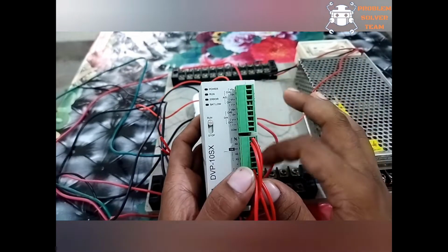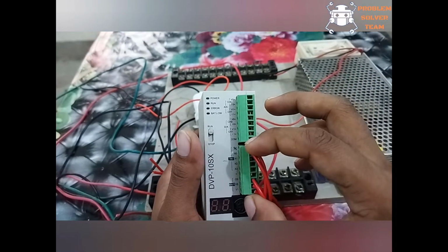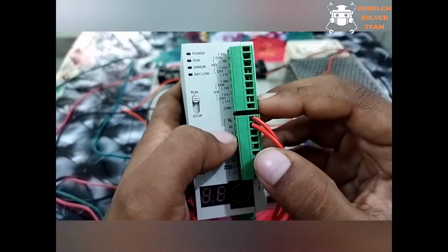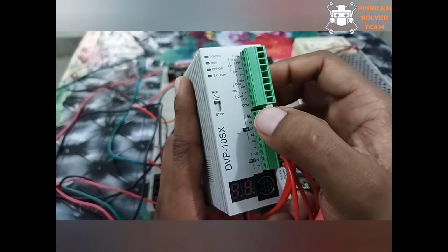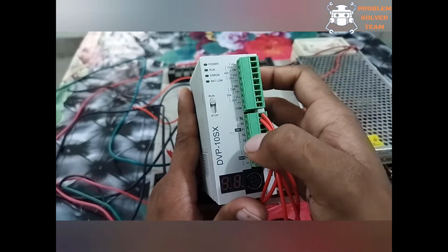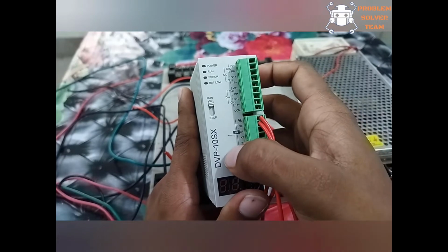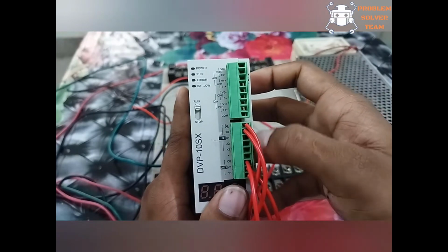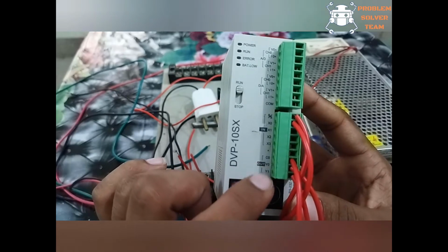Then the input and output section. This PLC has analog input output and digital input output. I will discuss the analog section in another video. In this digital section, this terminal is the input section and this terminal is the output section. The digital inputs are X0 to X3, a total of 4 inputs. This section uses an octal number system, the maximum input is 128, and this SS port activates the input section. In the output section, there are two digital outputs, Y0 and Y1.